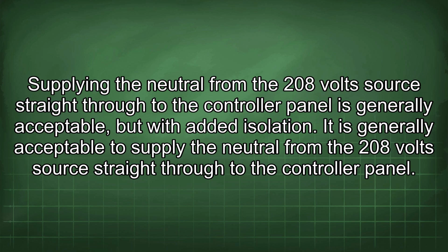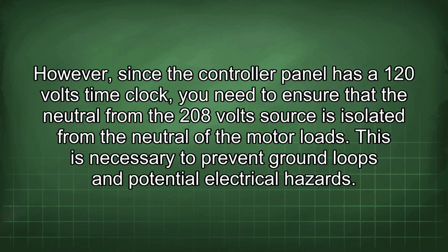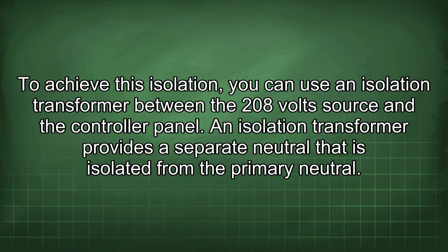However, since the controller panel has a 120 volts time clock, you need to ensure that the neutral from the 208 volt source is isolated from the neutral of the motor loads. This is necessary to prevent ground loops and potential electrical hazards. To achieve this isolation, you can use an isolation transformer between the 208 volt source and the controller panel. An isolation transformer provides a separate neutral that is isolated from the primary neutral.